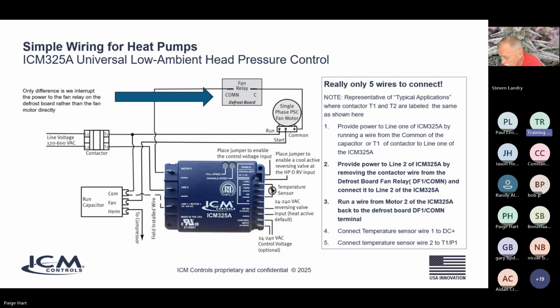So this is why we can't go directly from motor 2 back to the motor like we did before. What we have to do is, instead of taking the motor wire off the contactor, now we've got to look at the relay that's on the defrost board. So the defrost board is going to have a fan relay that powers the fan. We're going to look at the power going into that relay. Okay? And we're going to take that power that goes from the contactor into that relay at the COM terminal of the relay, or sometimes they're labeled ODF, outdoor fan 1, or DF1. Whatever that power is coming from the contactor to power that fan relay, we're going to take that power off and we're going to put it to line 2 of the ICM. All right. So the contactor again goes from T2 to line 2 of the ICM.